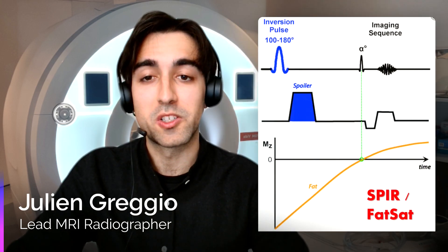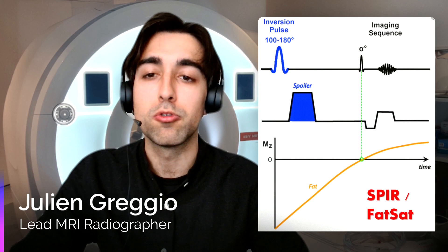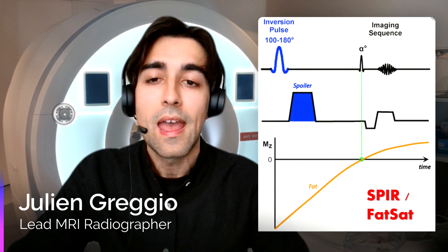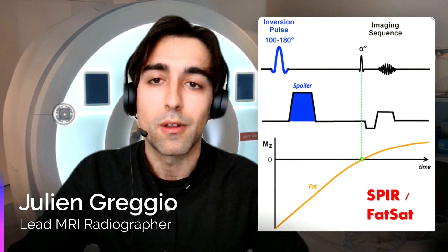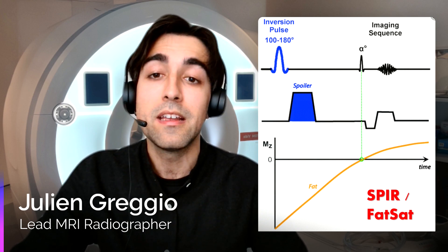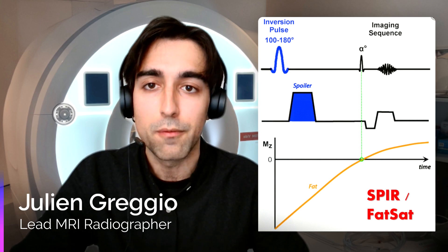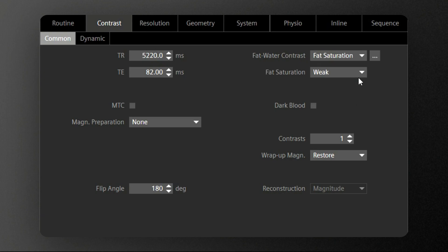Another possibility when it comes to suppressing the fat signal in MRI is relying on the SPIR technique, also known as FATSAT according to the MR vendor you are using. SPIR literally stands for Spectral Presaturation with Inversion Recovery. It employs a kind of hybrid approach, which combines the selective saturation of the fat signal using a specific radiofrequency pulse and the use of spoiler gradients. So the main difference with STIR is that this time the fat would be selectively saturated, rather than suppressing only those tissues that fall into a specific inversion time. To put this in practice, we just need to pick a T1 sequence from the scanner library and select the first option available in fat water contrast, namely fat saturation.